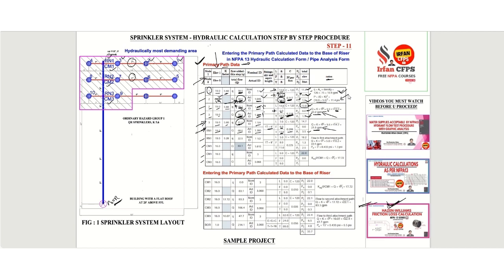We continue calculating up to CM2. At CM1 to CM2, both nodes are at the same elevation. The pipe size is 3 inches with an ID of 3.068, C-factor is 120 for black steel pipe, and total length is 9 feet. Pt = 18.2 + 1.3 + 2.5 = 22 psi. The equivalent K-factor at CM1 is calculated using Q ÷ √Pt = 83.1 ÷ √22 = 17.72.